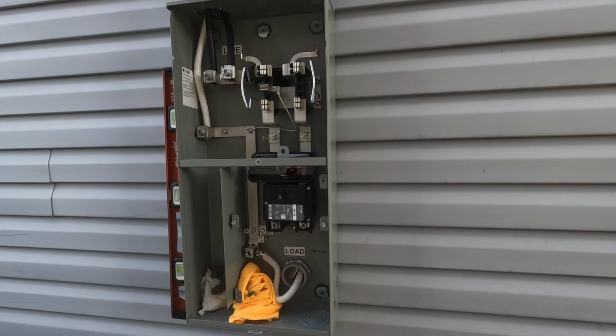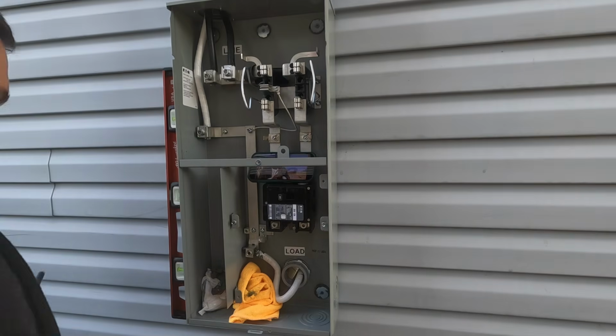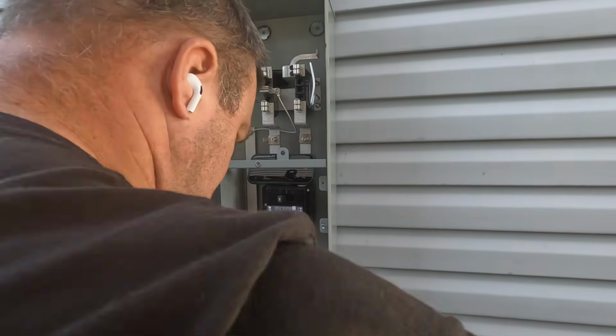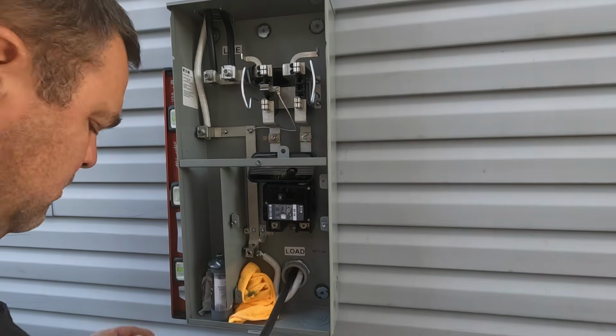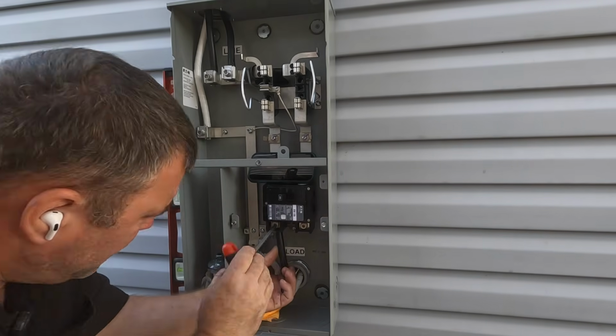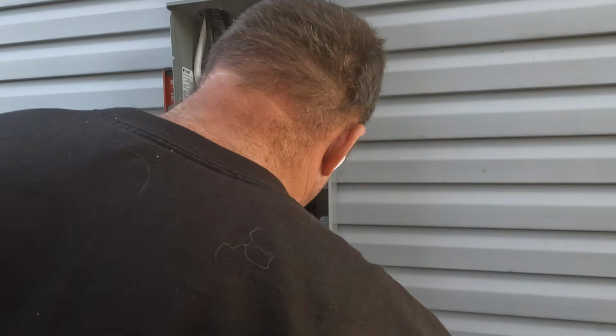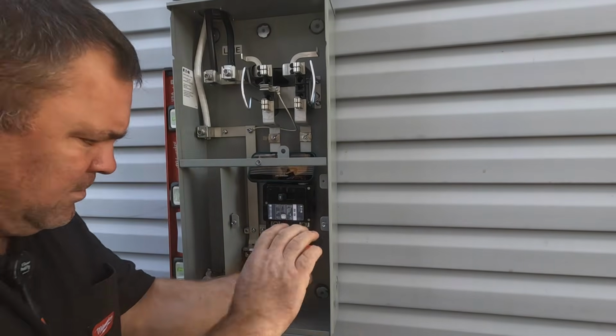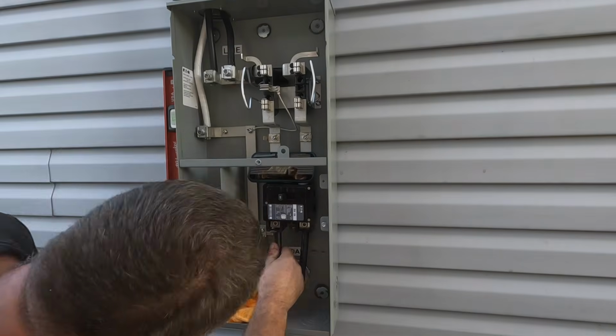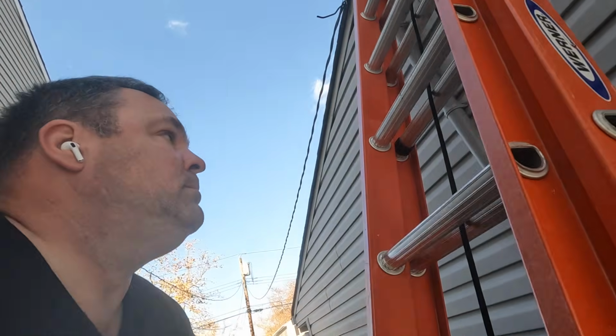This main disconnect is where all my grounding and bonding takes place. So what that means is my grounded neutral conductor from the service is here, and also the grounding electrode conductors from the water main and the supplementary ground rods all get attached inside this main enclosure here, where the main bonding jumper is installed, forming what's known as a solidly grounded system.